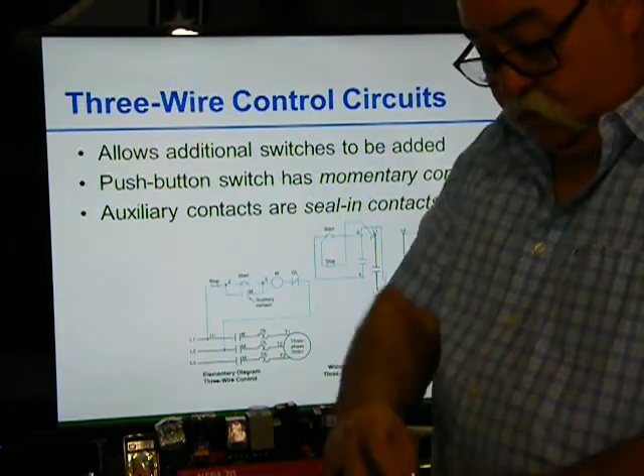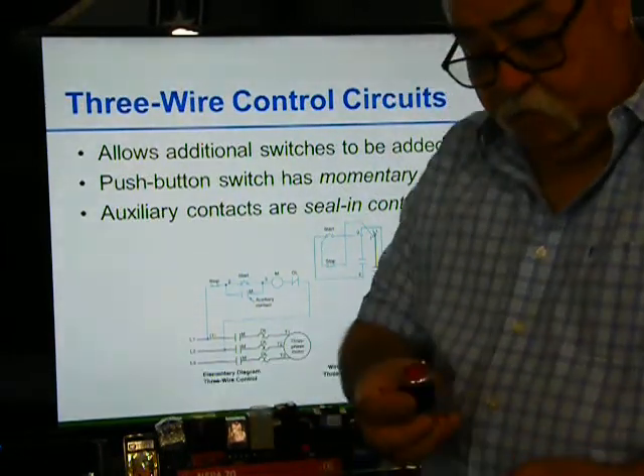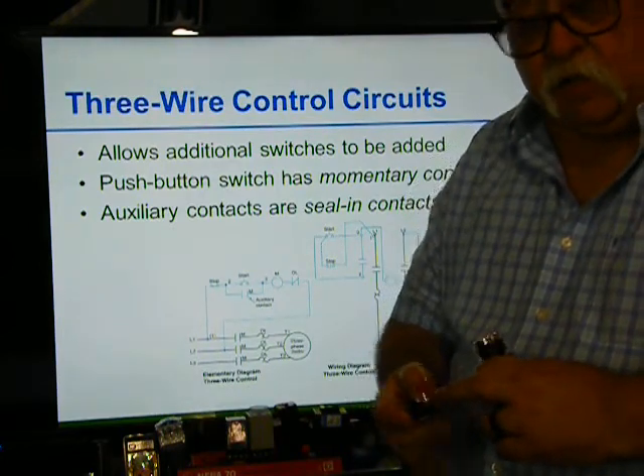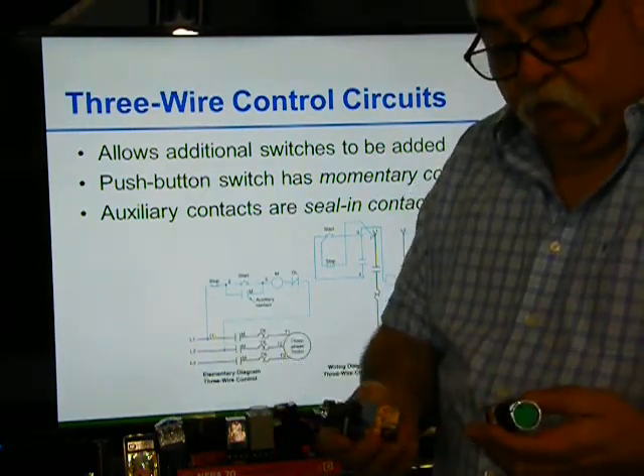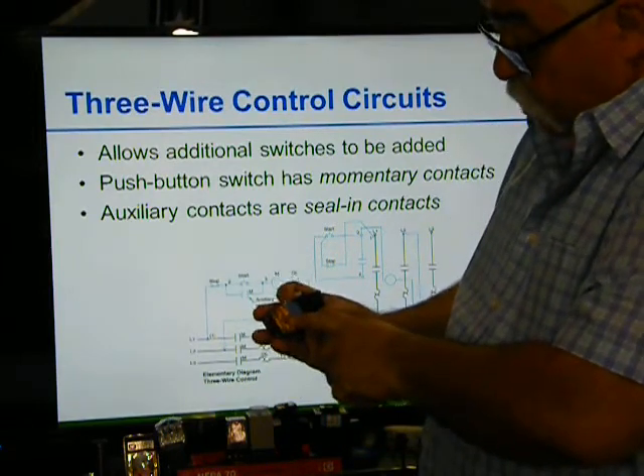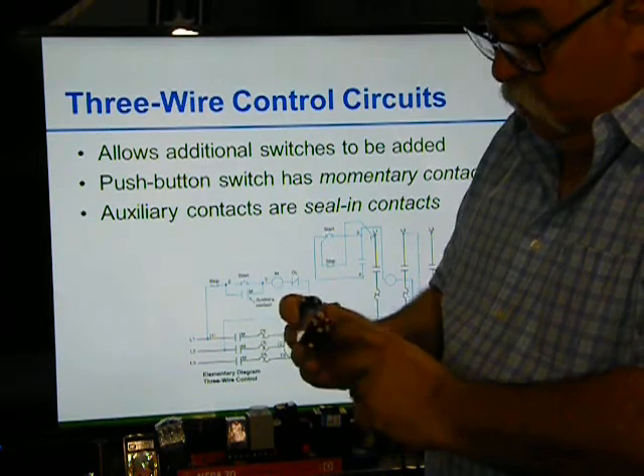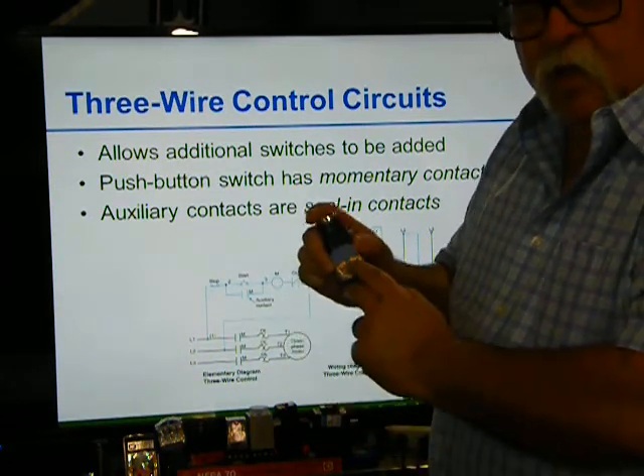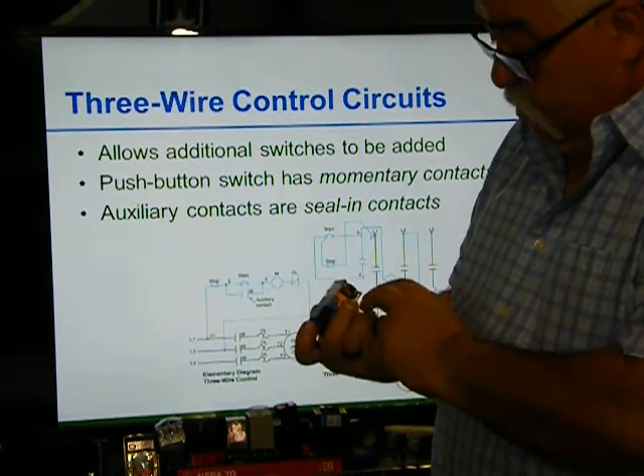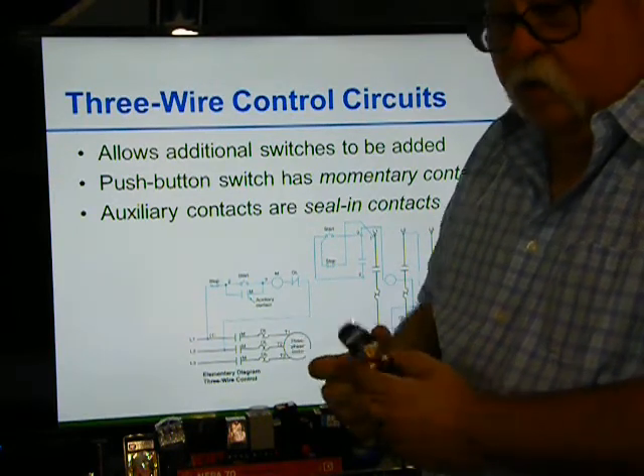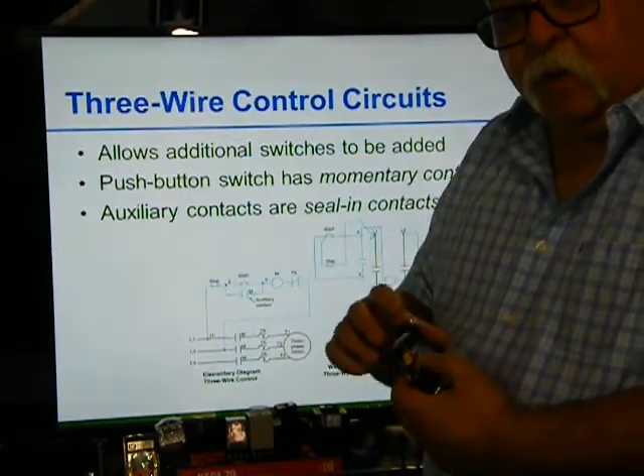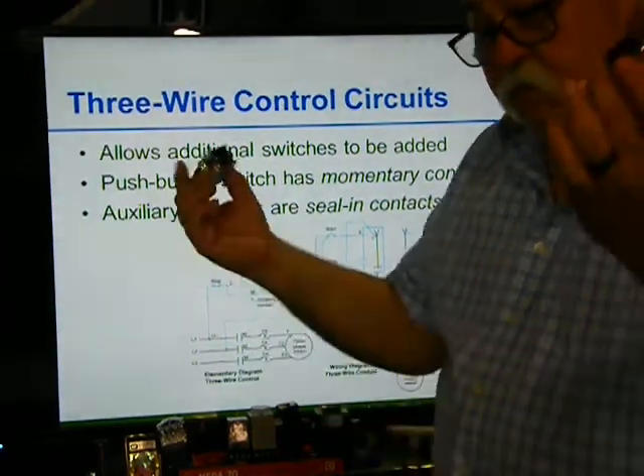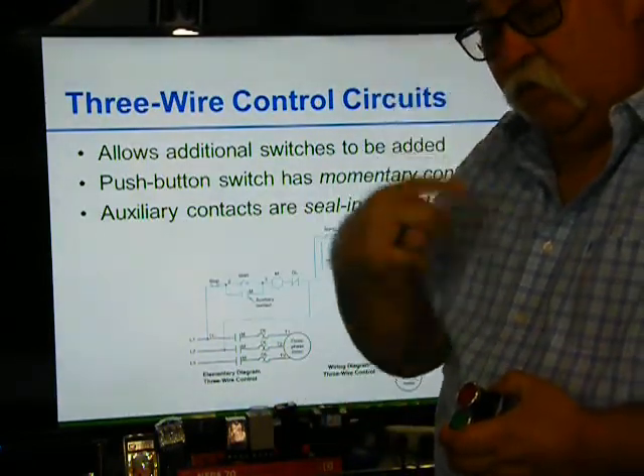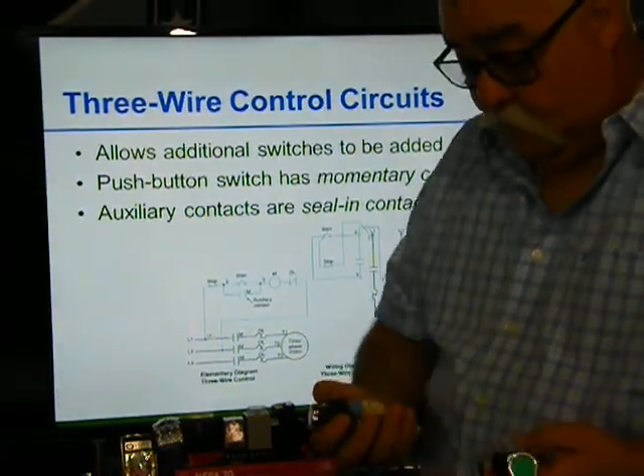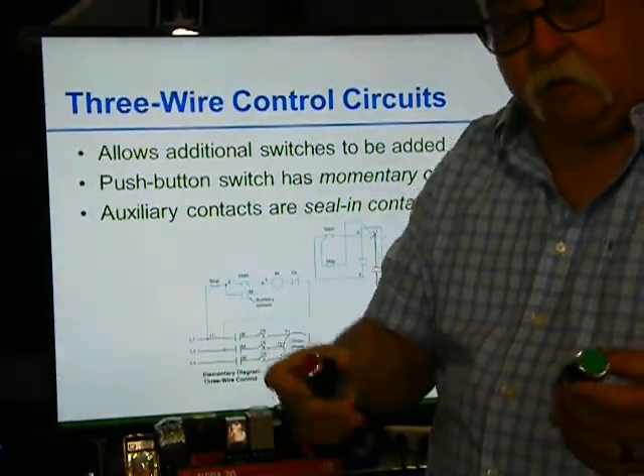So on this one, green is start, red is stop. It's just a piece of plastic that you can cover. So they're all the same. On one side it has a red side, and that is your 12 and your 11. On the other side it's green, and that would be your 23 and 24. Others have 1, 2 for the stop, 3, 4 for the go. So depending on the manufacturer, numbers can change. It's just numbers. It's that last number that we're looking at, the 1, 2, the 3, 4. So these two, there's no difference other than that little red cap.